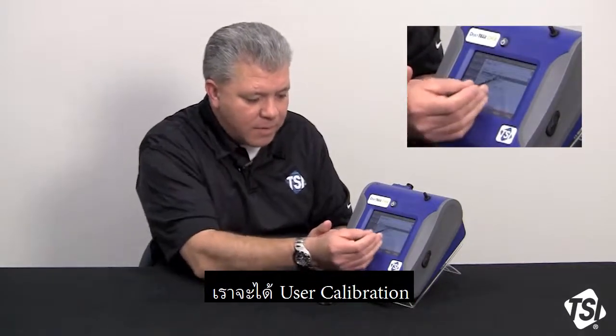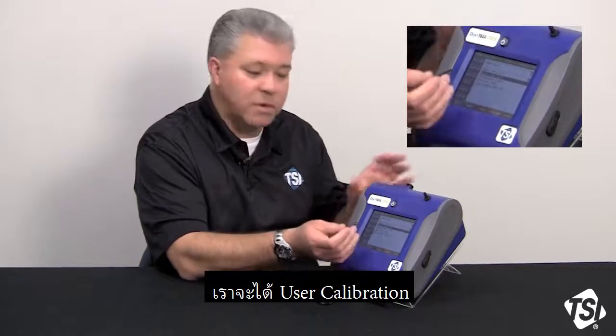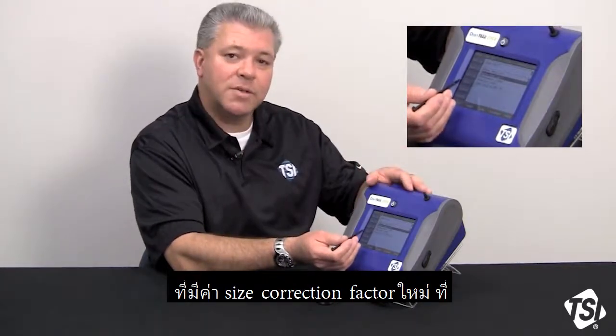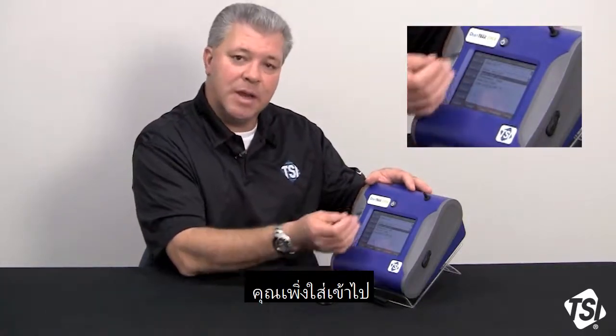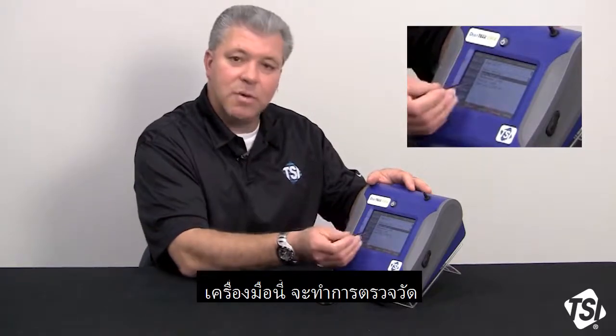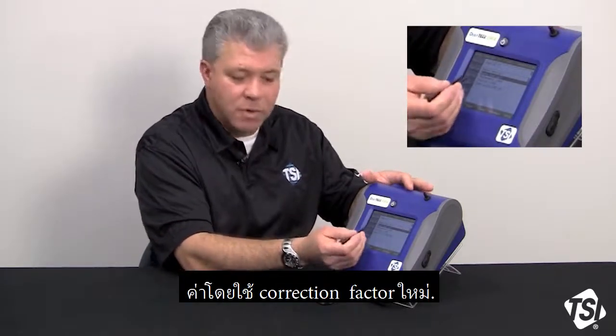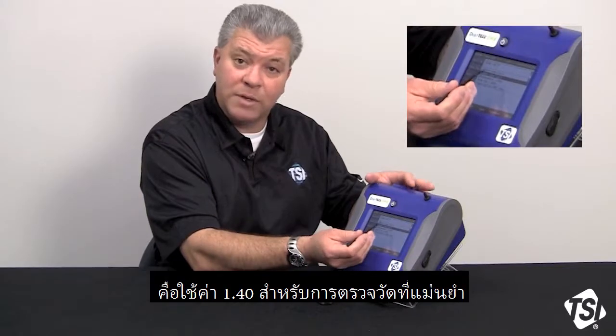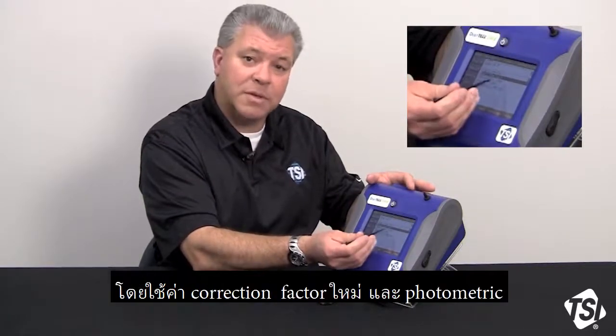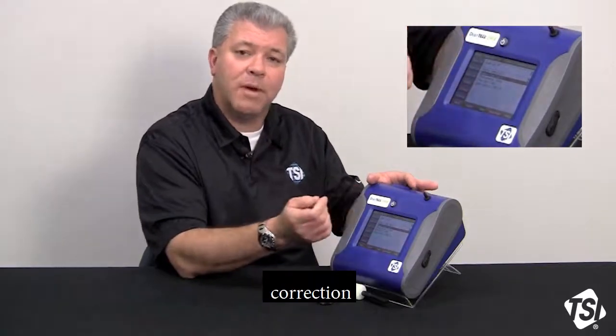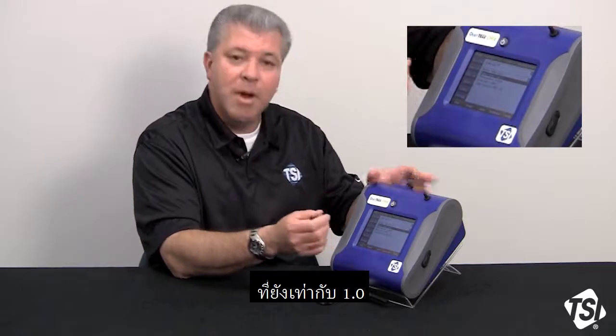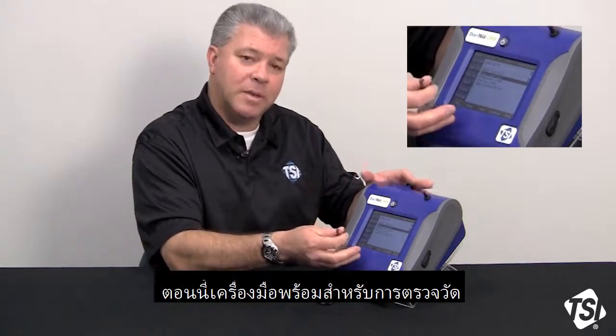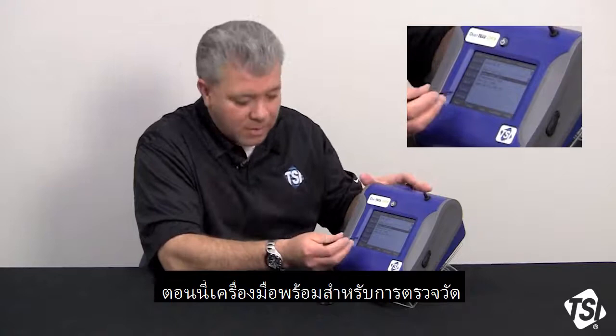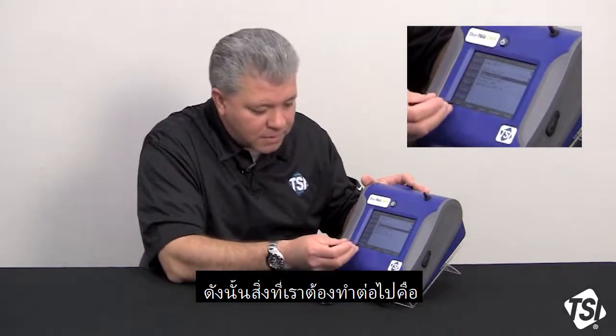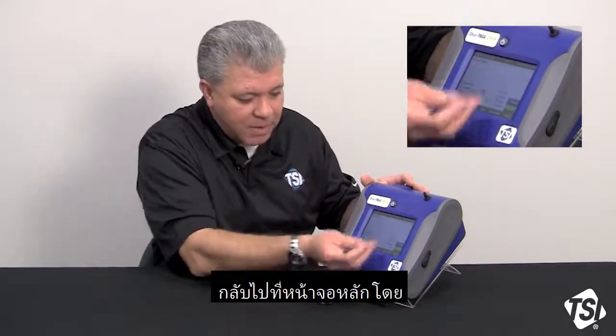And now this user calibration with this new real-time size correction factor that you just did is input into the instrument. This is going to be the new correction factor, so it would be 1.4, for example, for size correction factor, and your photometric correction factor is still 1.0, but that is what the instrument is now going to run at, okay? So now all we simply have to do is to go back to the main screen.